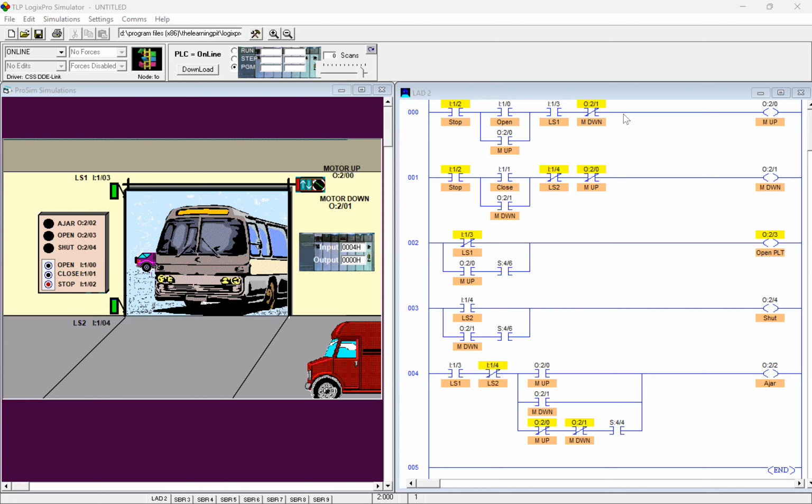But if I'm going up and I say I need to go down, I hit close once, it stops the thing from operating. When I hit close a second time, it's going to start to close. Same going down. If I'm closing and I want to go up, I hit the open, it stops it. When I hit the open the second time, I want it to go up. I have to flag the conditions of when the B3s are going to come into play.